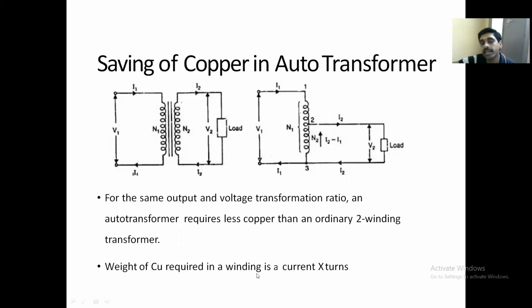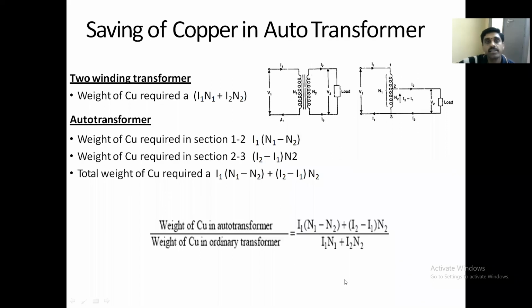The weight of the copper required in the winding is proportional to current times turns. Let us take it like this. For a two-winding transformer, the weight of the copper required in a normal transformer is I1 N1 plus I2 N2. That means, just like in terms of MMF, you can take it as the weight. This is the weight of the copper required.